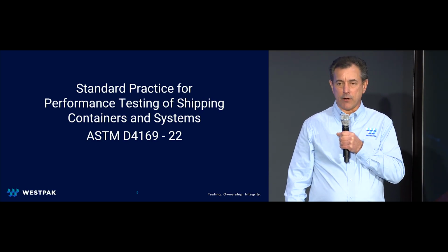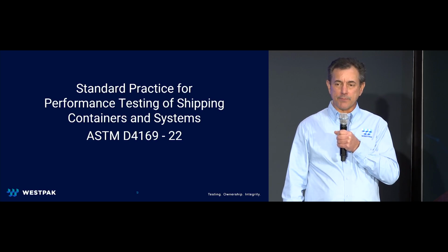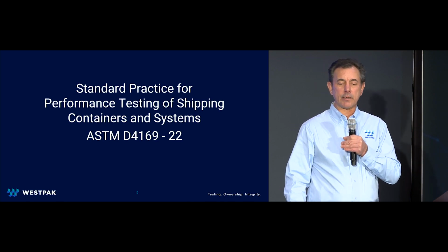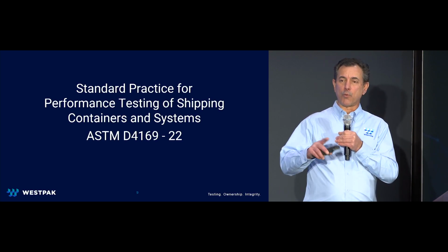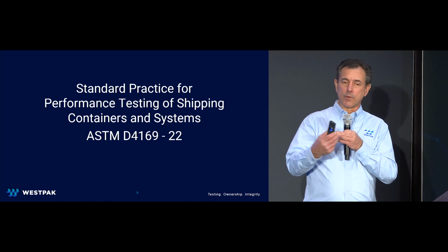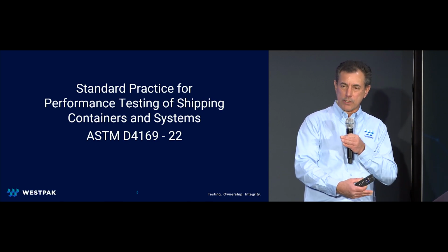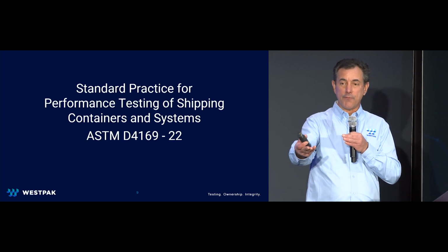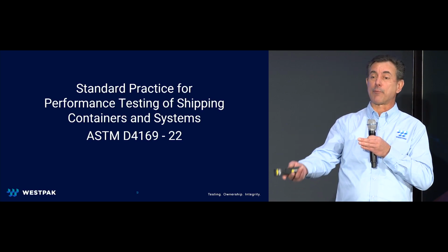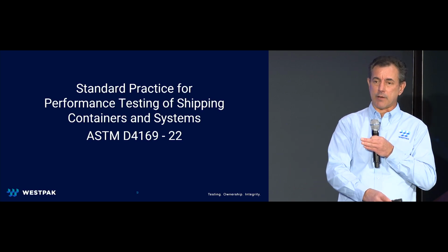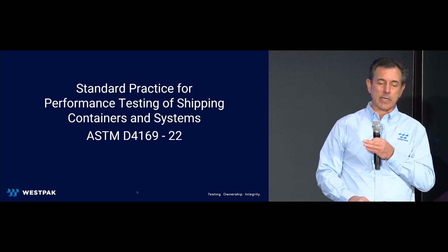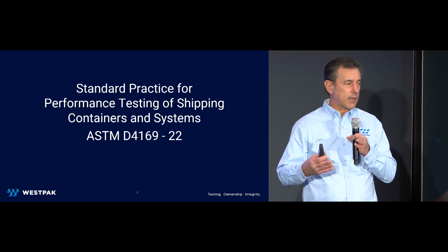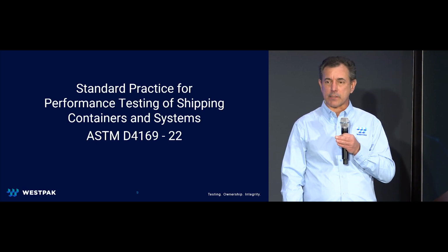How do I know which environmental condition to use for your product is the question. And that actually is not necessarily product specific, but what is in the environment. So again, we're testing for that really cold condition, anticipating a hot and humid condition and some sort of desert condition. If you need temperature control, that becomes a different standard. So we would take that to a different type of a standard and start talking a little bit about cold chain or condition, passive shippers, and that type of thing.